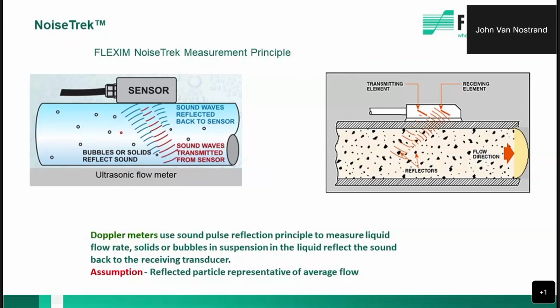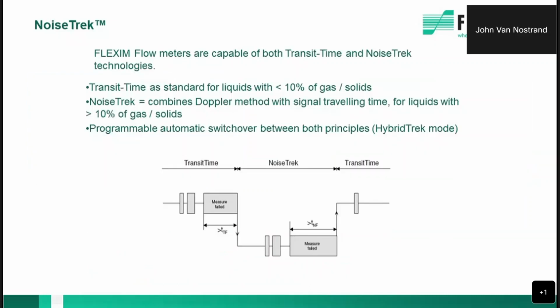What's nice about this is that we can switch back and forth. So we actually have a program in our meter that says, all right, if you get aeration or solids or something like that, switch to the NoiseTrek mode and then look for that transit time signal. And when it's present, switch back to transit time.